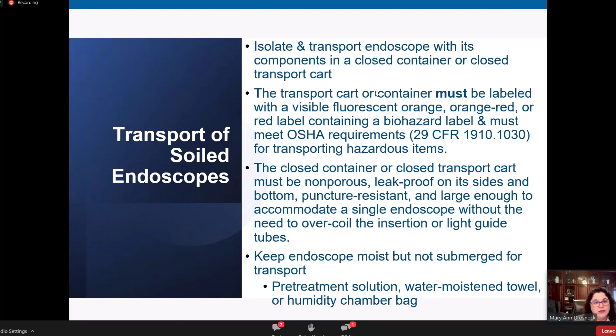There is a recommendation in there that the endoscope be kept moist but not submerged. And this was actually in the last ST91 also, but not a lot of people embraced this recommendation, but we did keep it in there, moist but not submerged for transport. And that is to keep those soils loose and hydrated so that they're more likely to be removed adequately during the full manual cleaning process. And again, we don't tell you how you have to do something, just what should be done. And then it's up to your facility to put a policy in place around that and pick a way to do these things. So we give examples like a pre-treatment solution or a water, not saline, moistened towel, or a humidity chamber bag for transport. And that does not allow you to get away with doing the delayed reprocessing unless you would have that evidence and validation from the manufacturer. But at least it keeps those soils moist for transport so that we can do a good job then during cleaning.